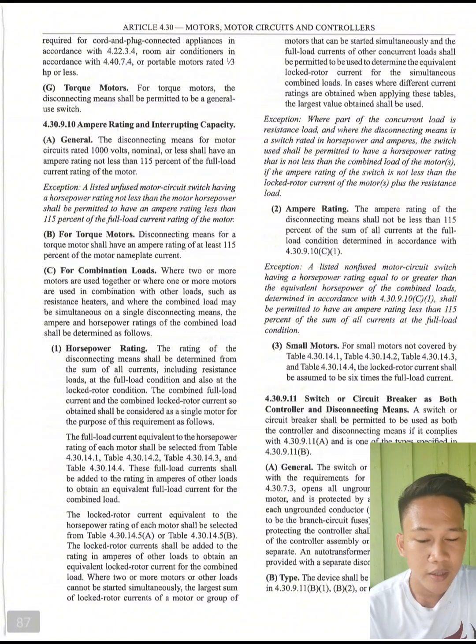The lock rotor current equivalent to the horsepower rating of each motor shall be selected from Table 4.30.14.5a or Table 4.30.14.5b. The lock rotor current shall be added to the rating in amperes of other loads to obtain an equivalent lock rotor current for the combined load.